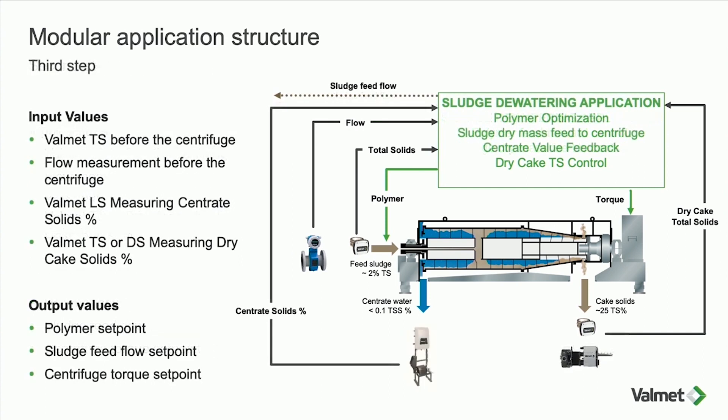With the full system — all measurements covering inlet, dry cake, centrate, and flow — we can control everything: mass flow to the centrifuge, polymer dosing into the sludge flow, and torque, all using the multi-variable controller. The goal is that 24/7 you are optimizing: keeping polymer to a minimum, keeping centrate to a minimum, and keeping dry cake solids as high as possible or within a certain process window.